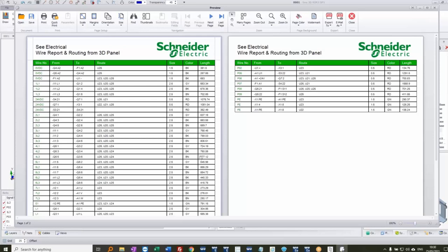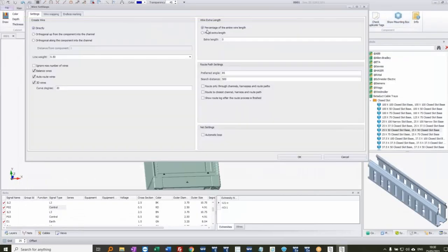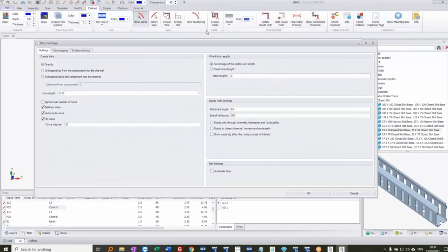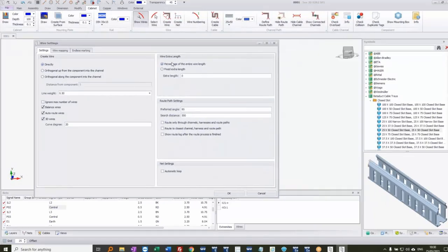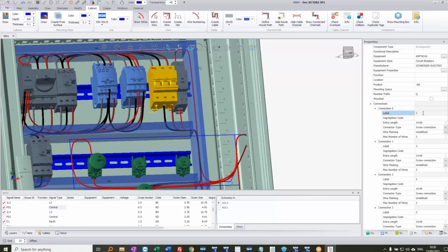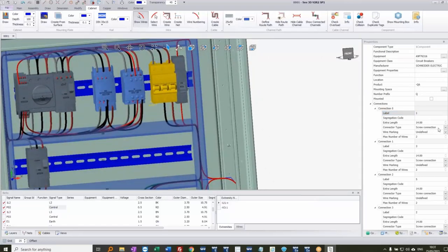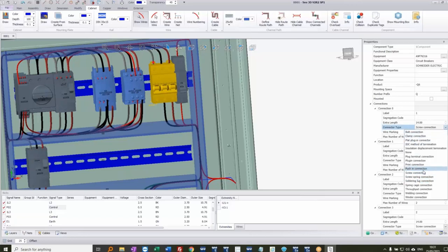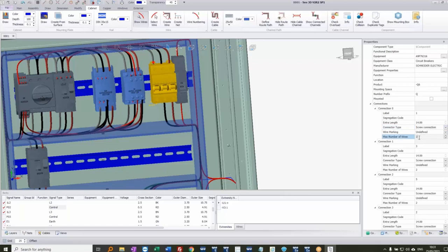When looking at wire lengths, there's a settings panel in the bottom right where you can add a percentage of extra wire to every wire — for example 10% — or add a fixed extra length such as 15mm per wire. Each component also has its own connection point properties — clicking on one shows a red dot indicating it already has an extra length of 14mm — accounting for wire that needs to be stripped back to fit into a screw termination. You can also limit the number of wires connectable at each point.